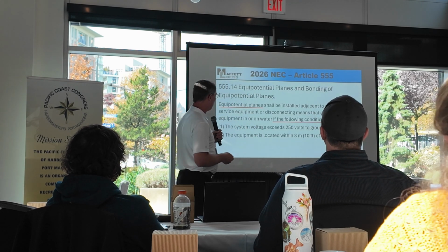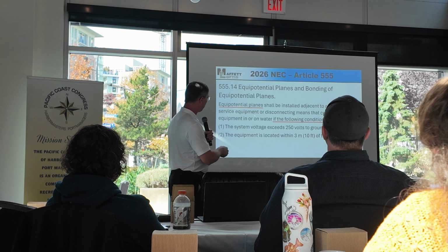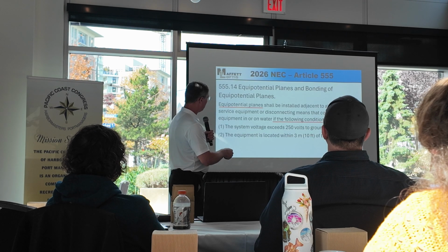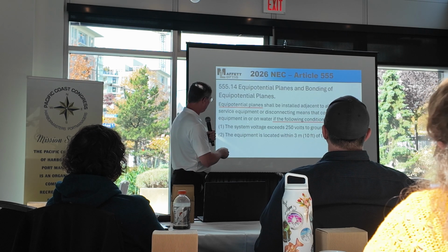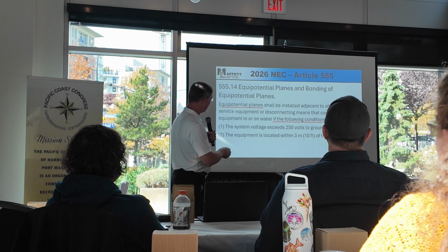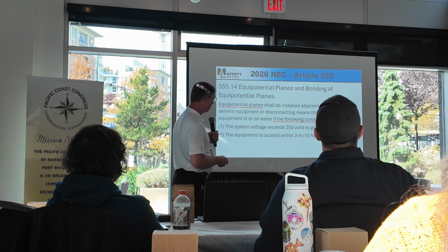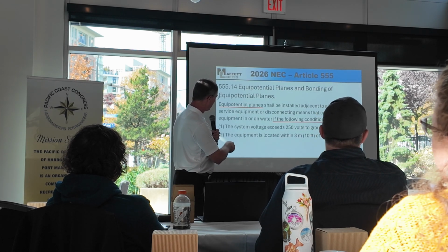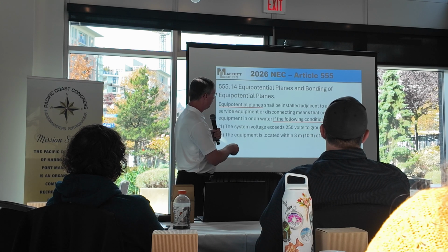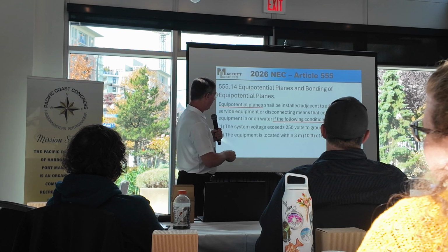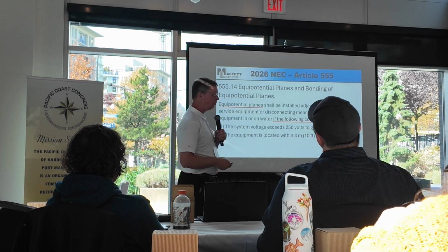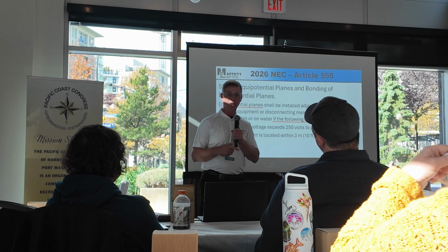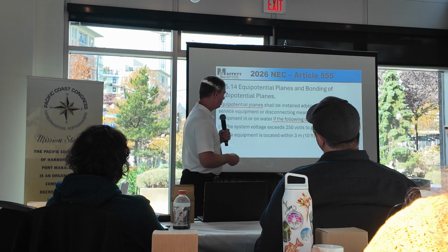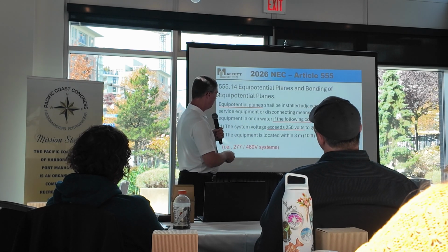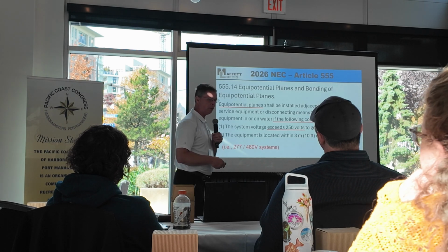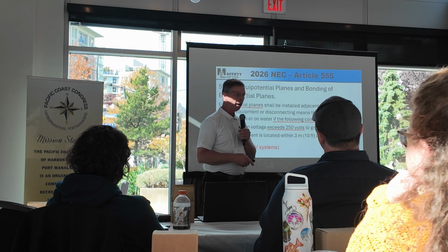And here, this is around outdoor service equipment, and it basically applies in the following conditions, which is an equal potential plane for outdoor service equipment. Both these conditions have to be true for this equal potential bond to be installed.